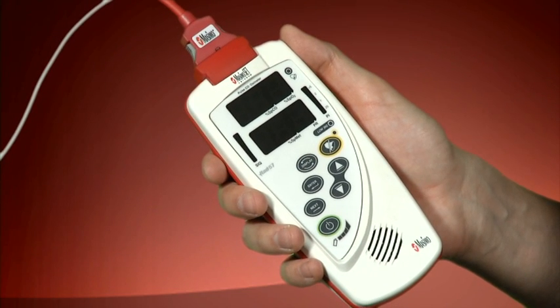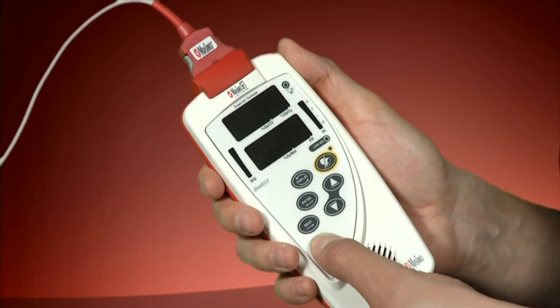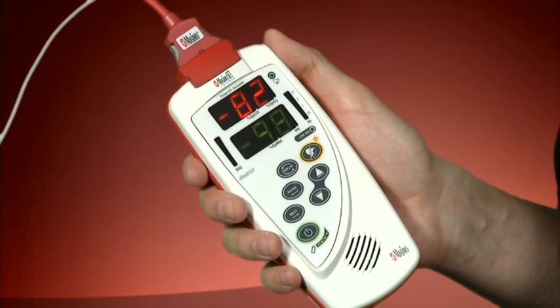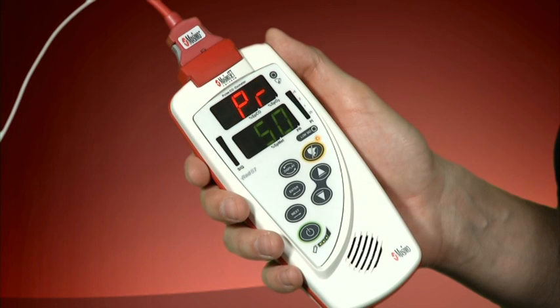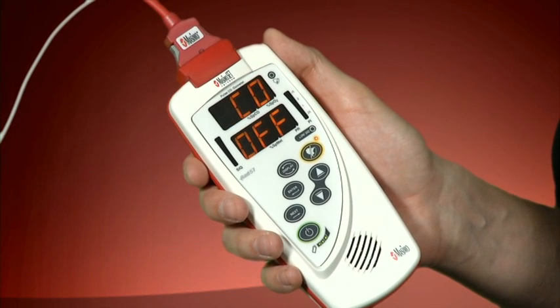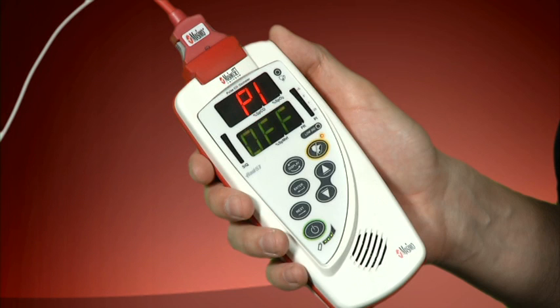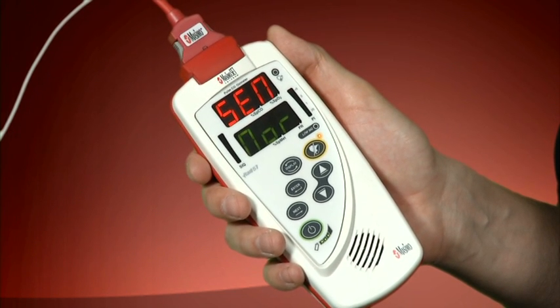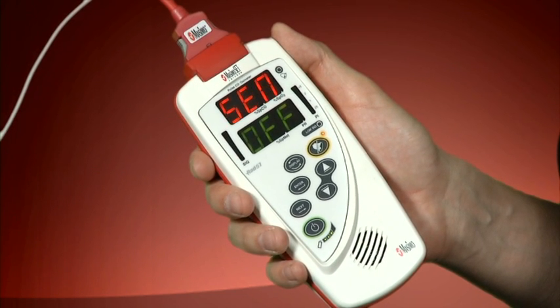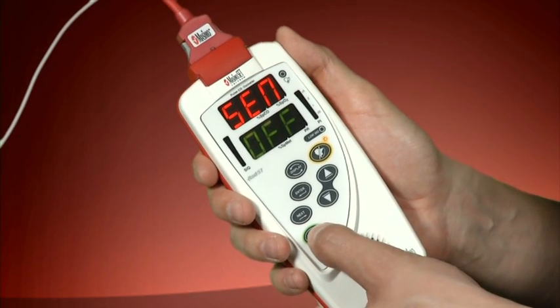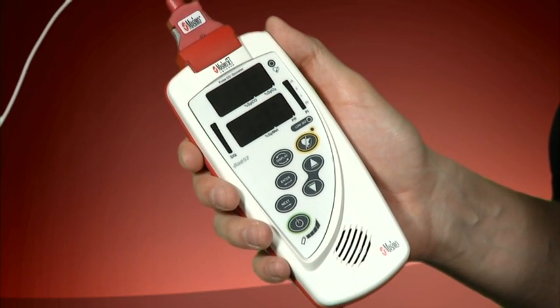To turn the Rad57 on, press the green power button. All LEDs will temporarily illuminate while an audible tone is heard. To turn the Rad57 off, press and hold the green power button for 2 seconds. You have the option of programming your Rad57 to automatically power down after 5, 10, or 15 minutes of inactivity, or to stay on until the device is manually powered down. In the default mode, the device will not automatically turn off.